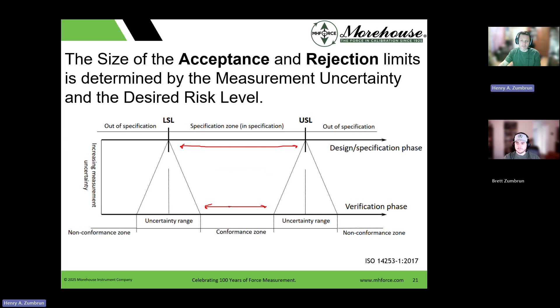And if I have the best equipment, like maybe, I'm going to be insulting here, Puka Nacua is a really great receiver. He might be the best receiver versus somebody else. Maybe JSN, yeah, okay, from Seattle. So maybe I can have a little worse of a throw up here and still have my receiver catch the ball. With my uncertainty being low, I have more room to say something's in tolerance and a better chance of it passing, which for you or your customer base means there's less chance of me dealing with a headache that somebody said, hey, this was bad when it's actually good, or this was good when it's actually bad. So all of this stuff, uncertainty is one of the biggest driving impacts for overall risk when we talk about likelihood and consequences.